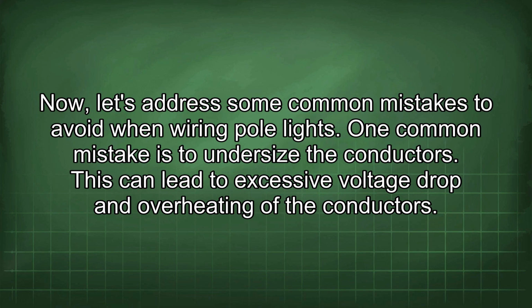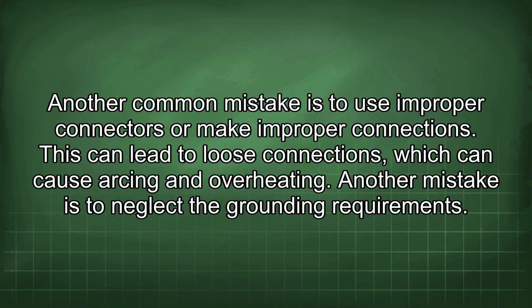One common mistake is to undersize the conductors. This can lead to excessive voltage drop and overheating of the conductors. Another common mistake is to use improper connectors or make improper connections. This can lead to loose connections, which can cause arcing and overheating.